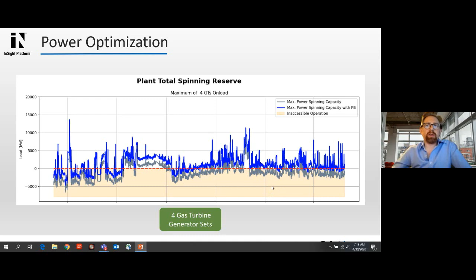We also evaluated this with 4 units in operation. With 4 units, only about 50% of the time would they be able to make the load, even with the advent of Power Boost. So in this case, we'd be looking at a minimum of 5 units of operation.